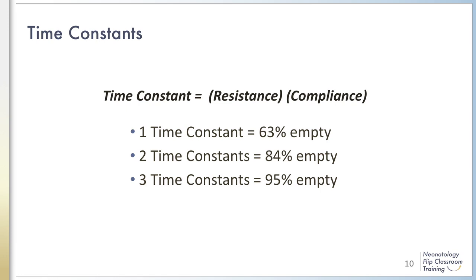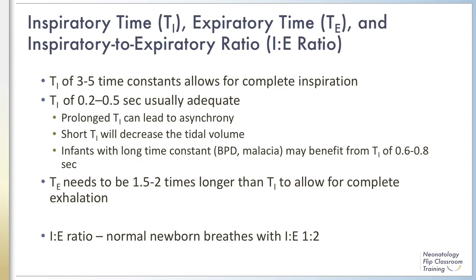Providing adequate expiratory time when on a ventilator can prevent breath stacking, air trapping, and overdistension. An inspiratory time of 3 to 5 time constants will allow for complete inspiration. For infants with normal lung compliance, a time constant of 0.09 seconds is average, and an inspiratory time of 0.2 to 0.5 seconds is usually adequate for full lung filling. Making the inspiratory time too long can lead to significant ventilator-patient asynchrony, while making it too short can decrease tidal volume, leading to hypercarbia and poor ventilation. Infants with longer time constants, such as severe BPD, may benefit from longer inspiratory times of 0.6 to 0.8 seconds.